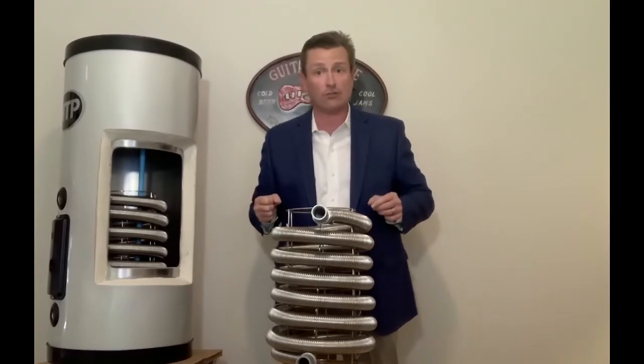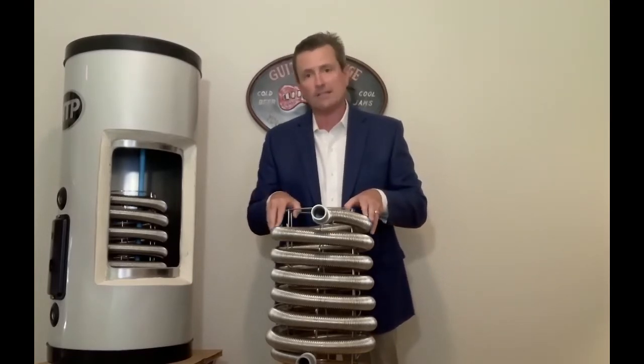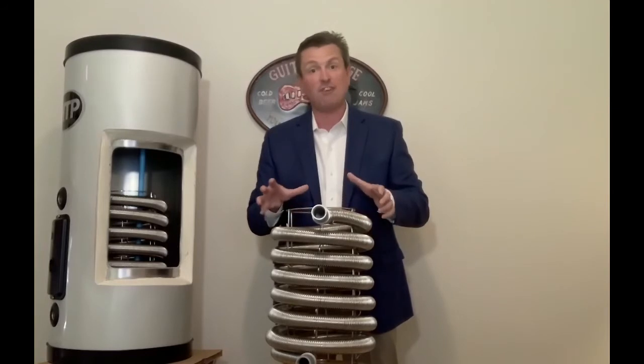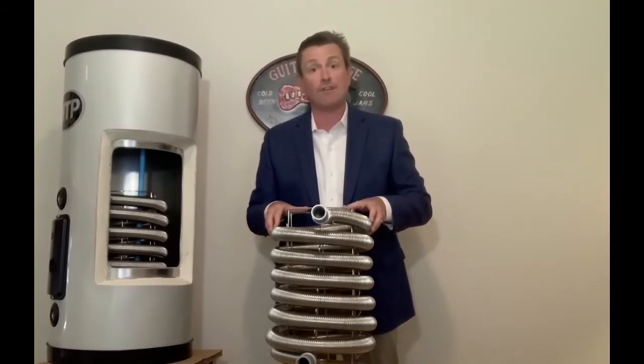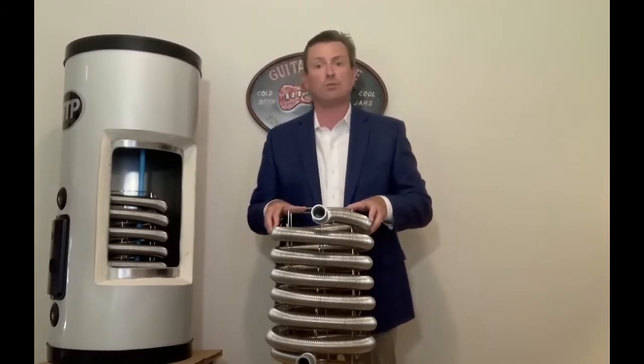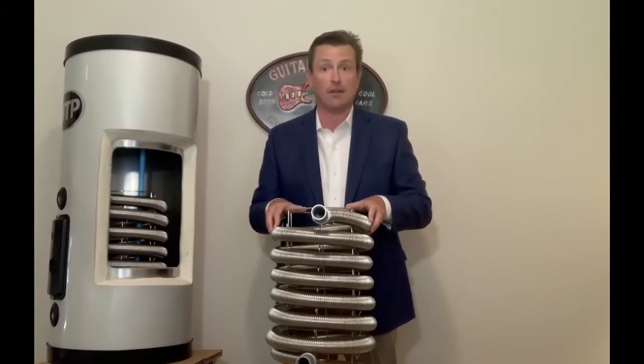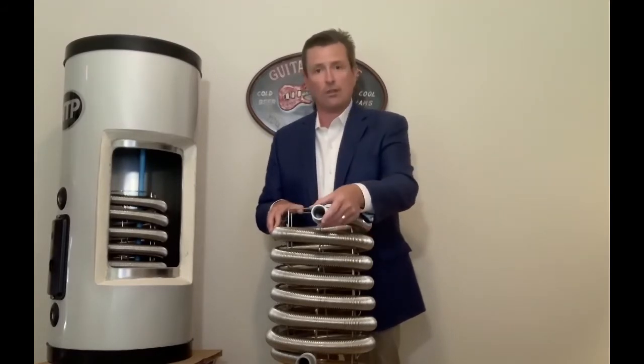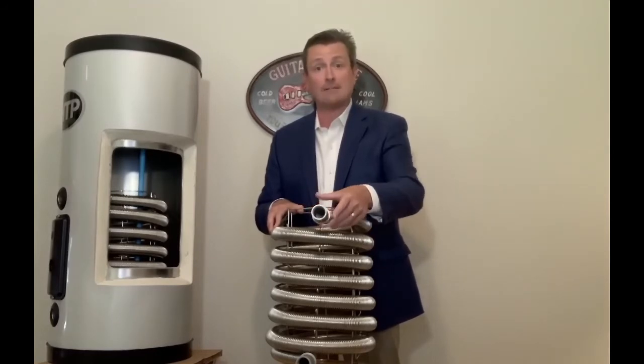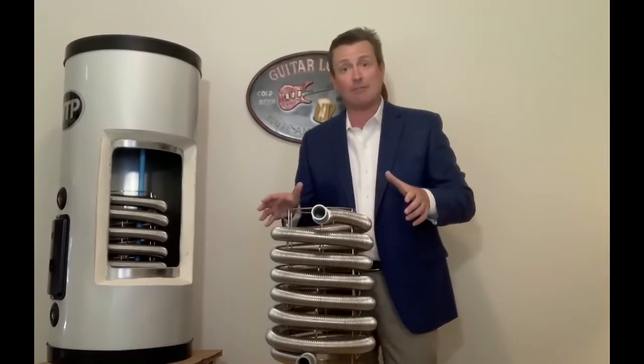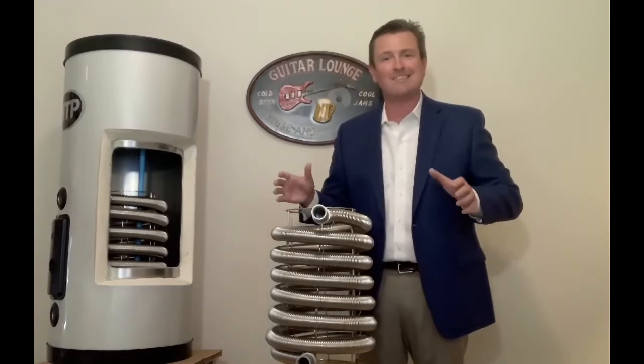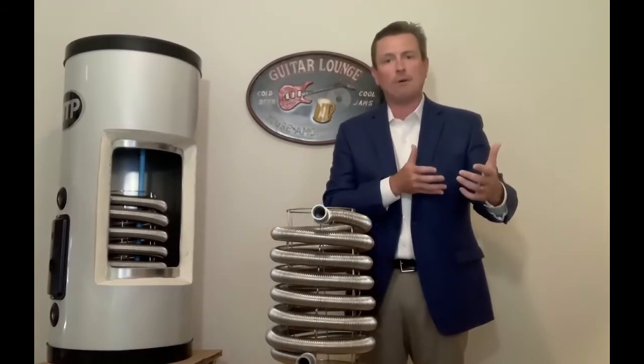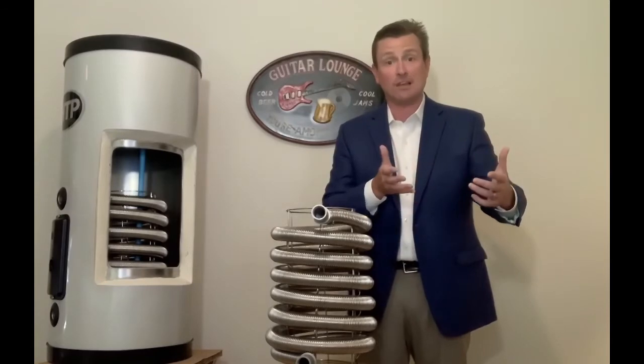And the corrugation is really important. A corrugated stainless steel heat exchanger is over 50% more conductive, over 50% more efficient than a smooth stainless coil like you might find in other products. Also, the larger diameter of the coil allows for a much lower pressure drop. At 10 gallons a minute through this coil, I'm only going to have 2.8 feet of head. This allows me to utilize much smaller circulators, like a 007e from Taco.